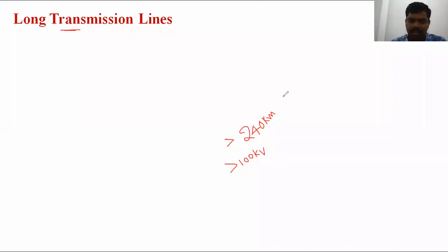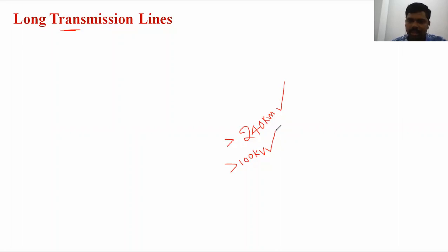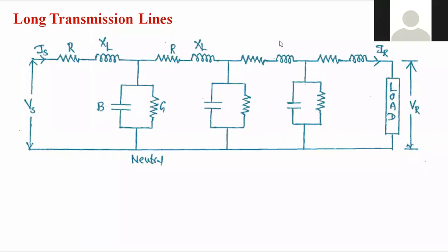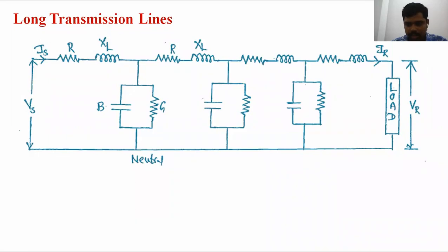In the long transmission line, the line length is greater than 240 kilometers — either 300, 500, or 700 kilometers — and the operating voltage is greater than 100 kV. Practically, it is considered for 132 kV, 220, 400, and 765 kV. In India, the maximum operating voltage for AC transmission lines is 765 kV. The long transmission line has four parameters: resistance, inductance, capacitance, and conductance.